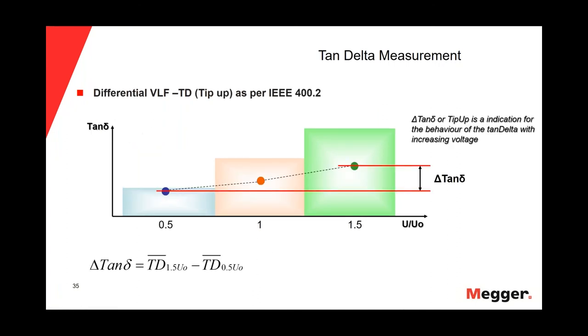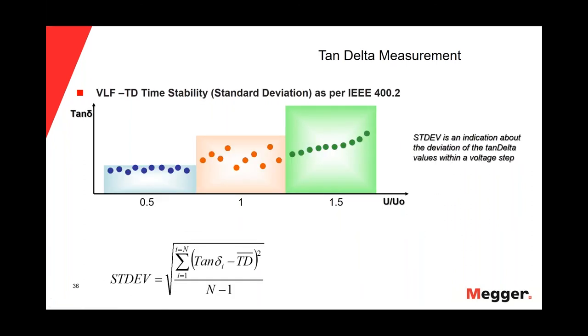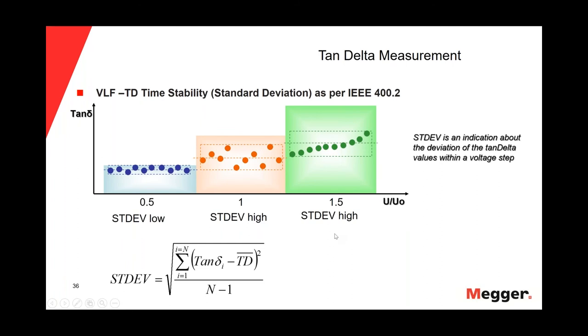The delta of the tan delta is the mean value at 1.5 U0 minus the mean value at 0.5 U0 — that is the second criterion. The third criterion is the standard deviation of the time stability of the tan delta, which measures how far or close the individual values are for each voltage step. In the first voltage step, we have a low standard deviation because the values are very close. But in the second and third voltage steps, the individual values are more dispersed.